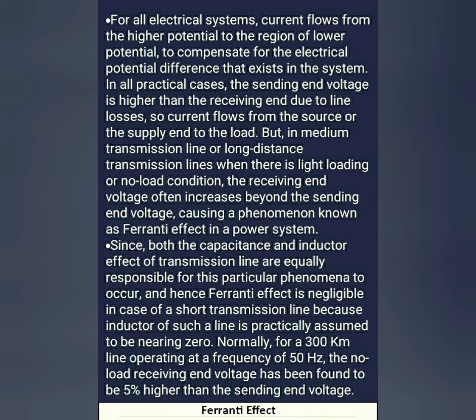So, to overcome this, nowadays we are connecting a shunt compensating device in parallel with that line at the receiving end. So, to overcome the Ferranti effect, this kind of shunt compensating device will be used. It will absorb the reactive power, so automatically the receiving end voltage gets decreased, or it comes to the level of your sending end voltage, and from this the Ferranti effect gets reduced.